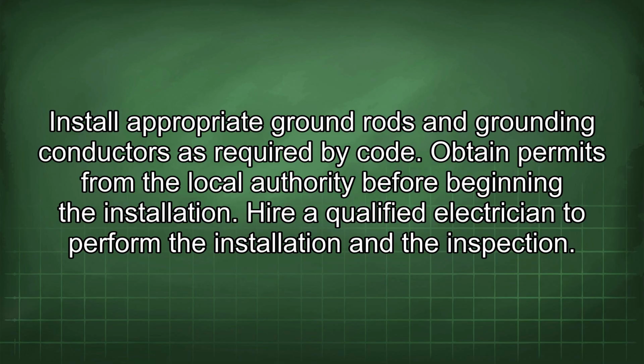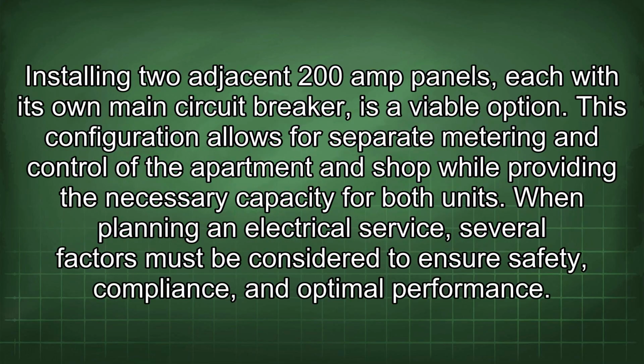Obtain permits from the local authority before beginning the installation. Hire a qualified electrician to perform the installation and the inspection. Installing two adjacent 200 amp panels, each with its own main circuit breaker, is a viable option. This configuration allows for separate metering and control of the apartment and shop while providing the necessary capacity for both units.